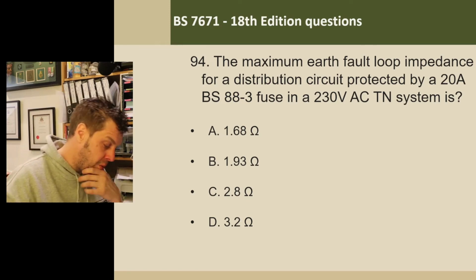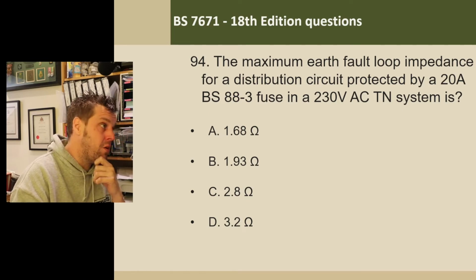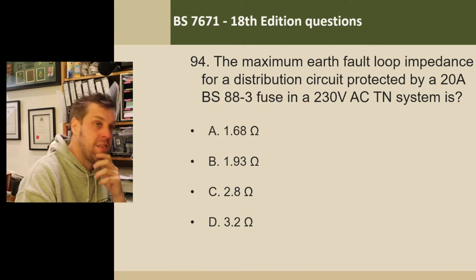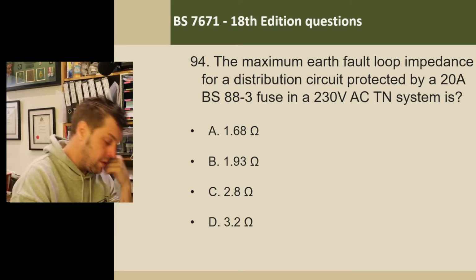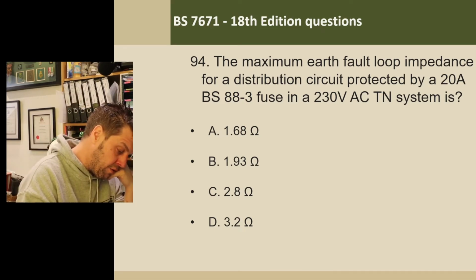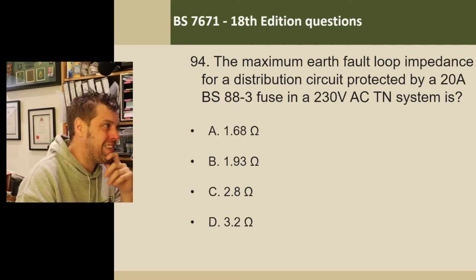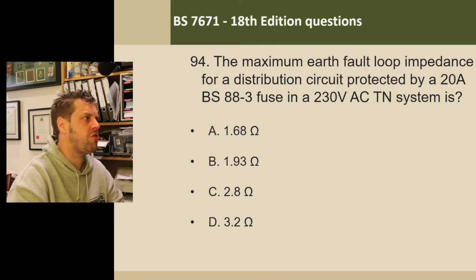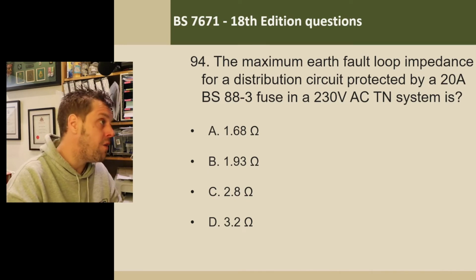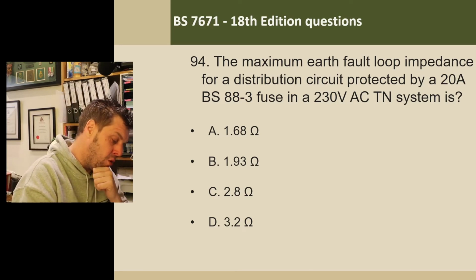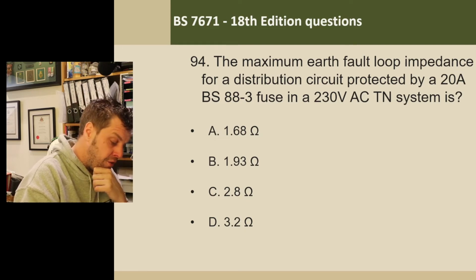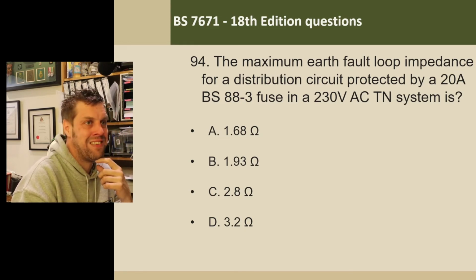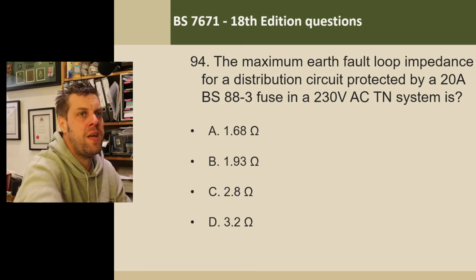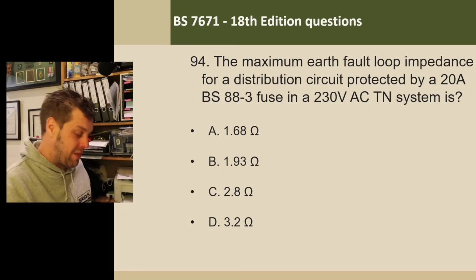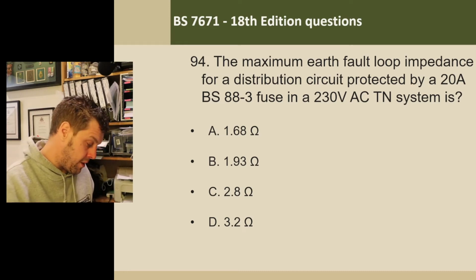However, table 41.2 gives me in numbers the maximum earth fault loop impedance, of a question, for fuses with a 0.4 disconnection time. Now, a 0.4 disconnection time is a final circuit, not a distribution circuit. So I don't think it's table 41.2, because that says maximum earth fault loop impedance for fuses for 0.4 second disconnection time, which is what I'm looking for. Well, this question is asking me for a distribution circuit. That would be 5 seconds. So maybe it's not 41.2.